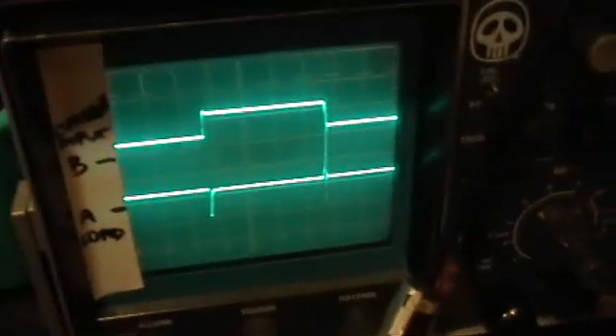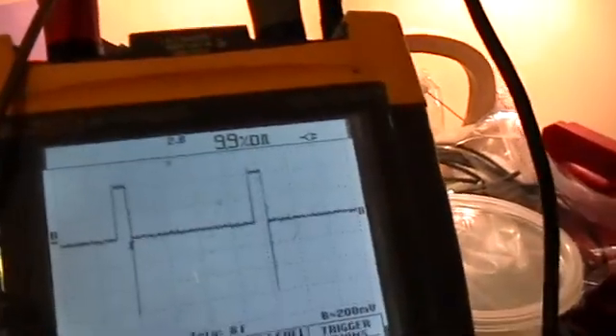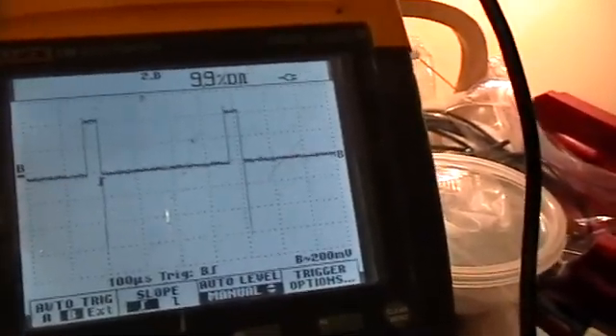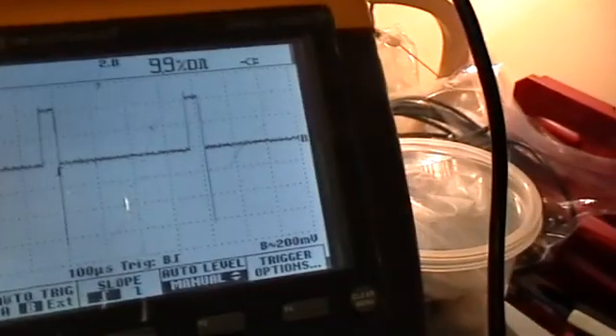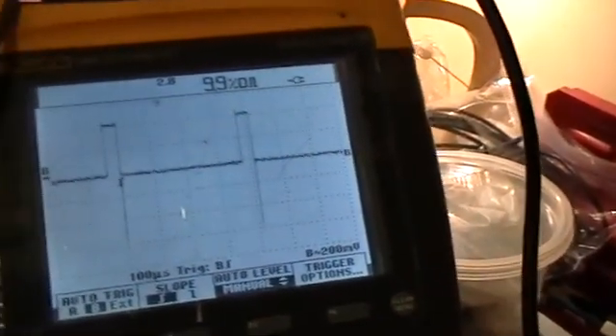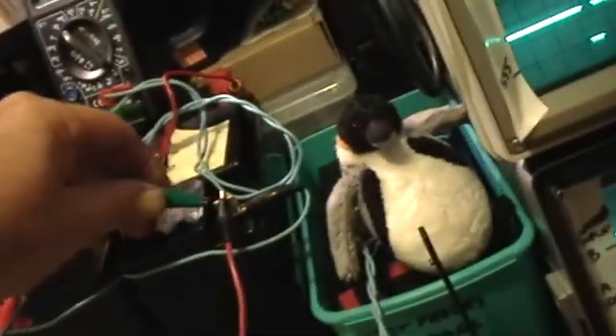Now, I'm going to connect and disconnect that, and we'll see how the scopes behave. Oh, let me put the other trace on here. You see any difference there? I don't. What about on the Fluke? That's grounded, earthed rather. That's not. That's earthed. That's not. So, there's no difference, as far as the scopes go, if your system is properly hooked up, properly energized, and properly isolated. You can have it hooked to the ground, earth ground, or not.